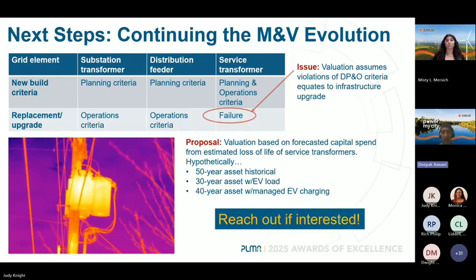Looking at a hypothetical example: suppose your service transformers are trending at a 50-year useful life, failing after 50 years in service. After EV adoption, using whatever forecast you have, like the 288,000 number by 2030, maybe you estimate that loss-of-life rate trending toward 30 years. If you mitigate that with VGI measures such as time-of-use rates or managed EV charging, hypothetically you reduce that impact to a 40-year useful life. So the benefit of managed charging is the additional 10 years of life you get out of that service transformer, which directly translates to a different trajectory for your capital spend forecast.